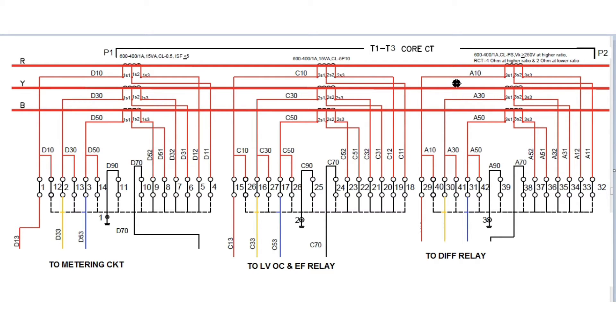This is the primary side. There are three number of cores. One is the metering core, designated as D ferrule. One is the core taken for the overcurrent and earth fault relay, designated as C ferrule. And another core taken for the differential relay, designated as A ferrule.